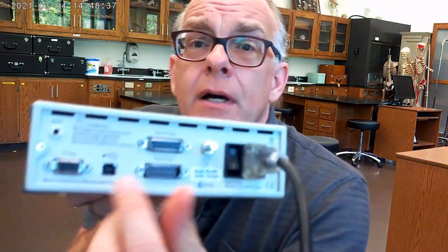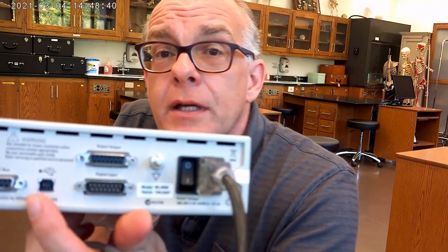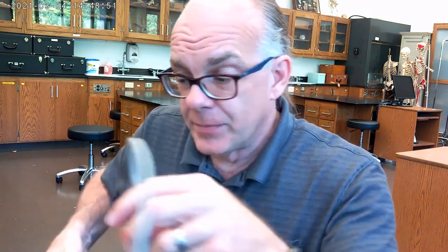The second cable that you're going to need is a USB cable to connect the Power Lab system to the computer. It's got a standard USB at one end, and a rounded-off rectangular connector at the other end. This plugs into the back of the Power Lab system, where you should see a USB symbol with the connector. Because of the rounded-off rectangle, it's only going to fit in one way. Don't force it, it should slide in if you've got the orientation right. Once that's plugged in, connect the USB end into the USB port on the back of the computer.